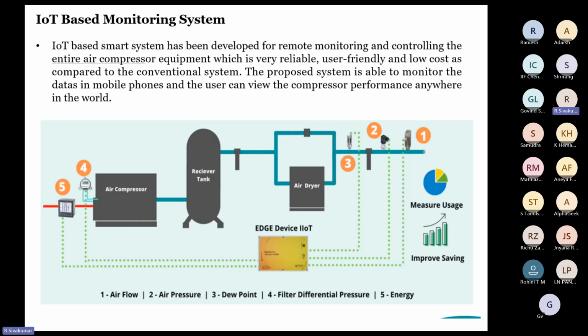Now there is a thermal mass flow sensor type and an IoT, Internet of Things, monitoring system available. It is practically possible to see your compressor performance. Most foundries have compressors installed more than 5 years, so they can go with the IoT system to monitor present compressor performance, because the manufacturer says 250 CFM or 300 CFM, whatever it may be. What is the actual CFM produced by the compressor? What is the energy, pressure? Everything can be monitored, and based on that, management can decide whether to go with a new compressor. The leakage quantity is also quantified with this IoT system. It is a very helpful tool. By adopting this kind of IoT-based monitoring system, a minimum of 10 to 15% energy savings can be achieved in the compressor alone.